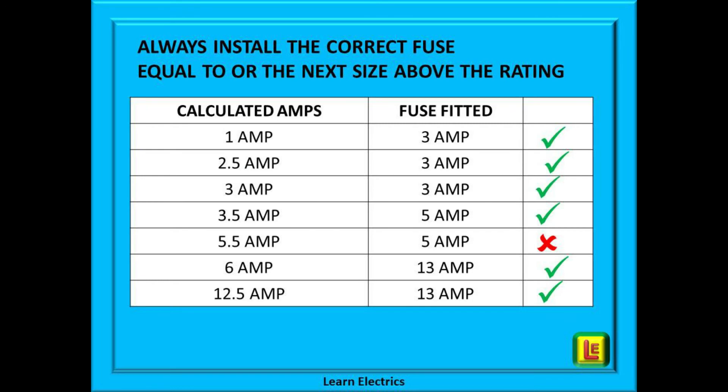On this table we have shown some examples of the calculated amps and the size of fuse that should be chosen. You can see that for 1 amp, 2.5 amps, or even 3 amps, we should choose a 3 amp fuse. If your calculation gives 3.5 amps then we must go to the next fuse size above, which is 5 amps. If we calculated 5.5 amps, we must not fit a 5 amp fuse — it will only blow when you plug the appliance in. For 5.5 amps we must select a 13 amp fuse. A 6 amp rating would also require a 13 amp fuse, and as shown previously, for 12.5 amps we also choose a 13 amp fuse.